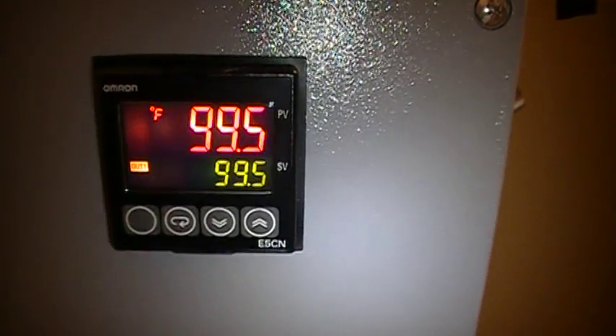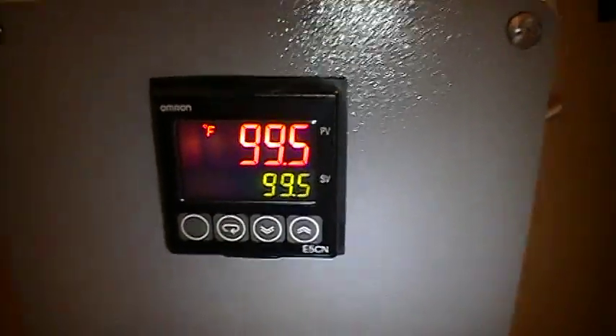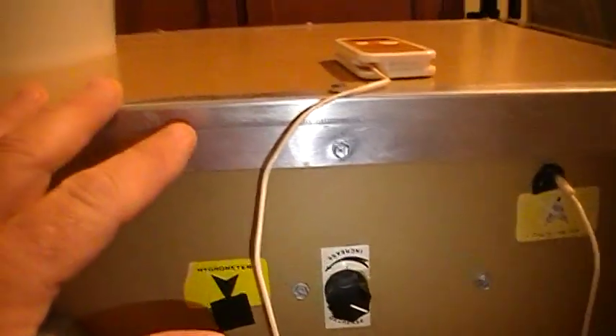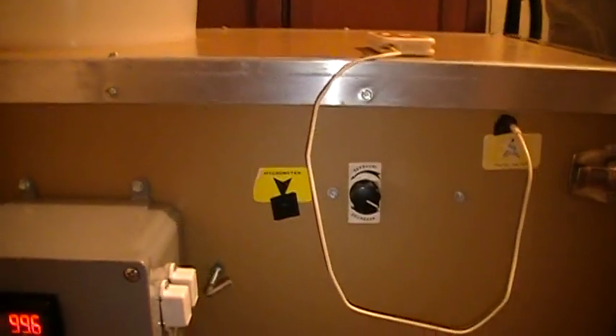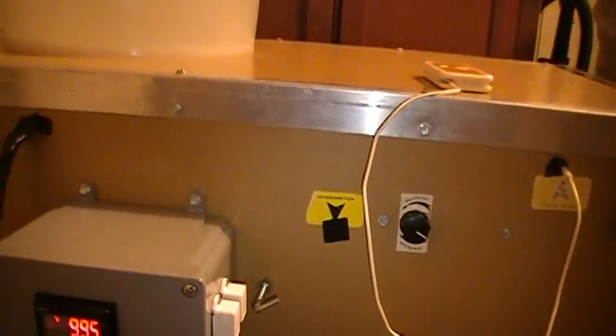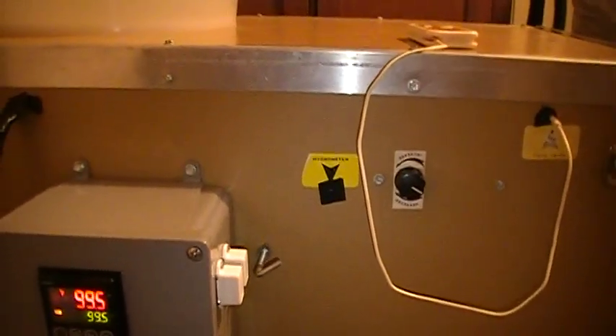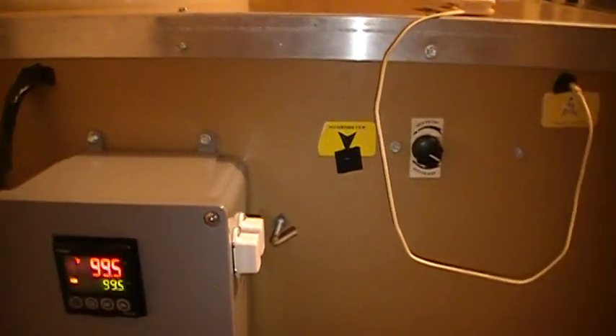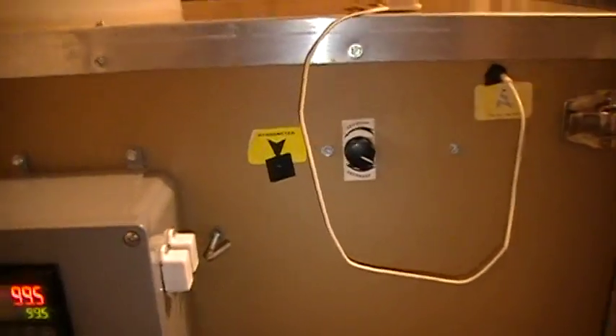Now, I'm sure some of you are wondering, well, now you're showing 99.5 there, and up here on your little Brinsea you're back at 101.1. Well, just by the nature of this incubator, obviously the top of the incubator has got to be a little warmer than further down on the incubator in order to accommodate for the heat loss in the unit, and generally your forced air type incubators are much more uniformly heated than a still air incubator. You don't have the layering of the heat.